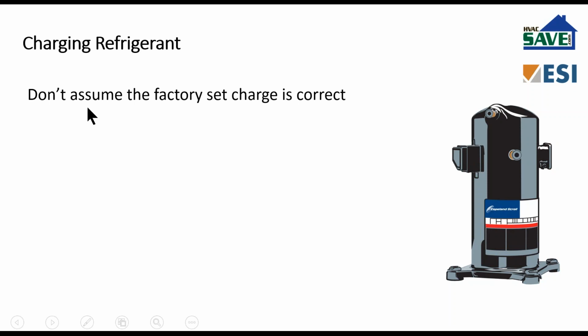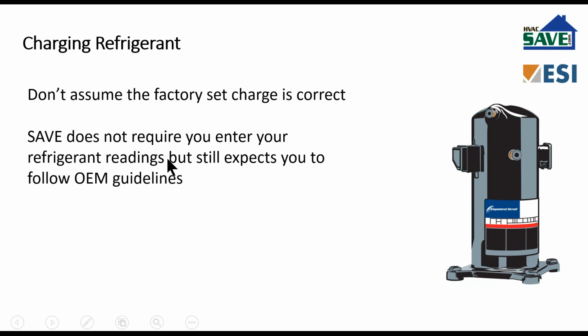You're a professional, you're a technician, your job is to make adjustments in the field, and you'll have a line set out there and you'll need to adjust the refrigerant charge based upon that line set. Now, SAVE does not require you to enter or provide us your refrigerant readings, superheat, subcool, or alternative. But we still expect that you will follow the OEM guidelines.